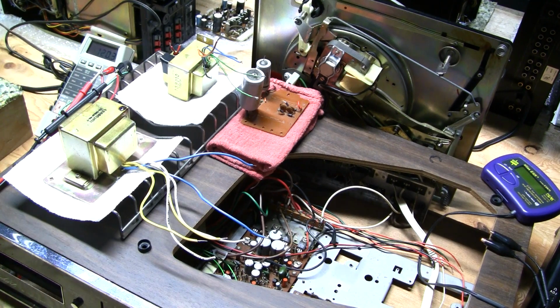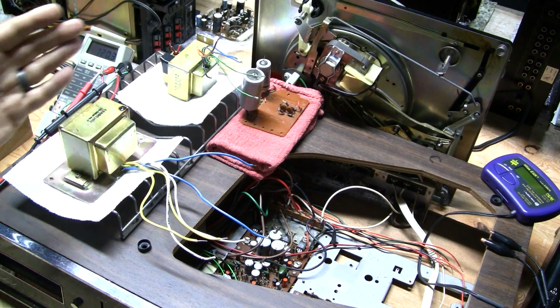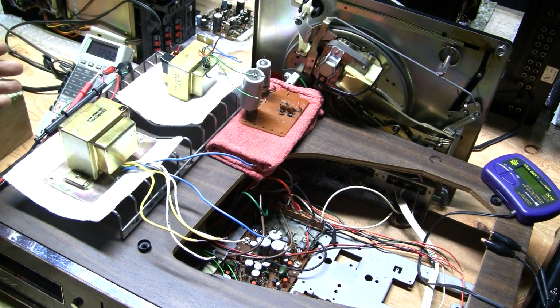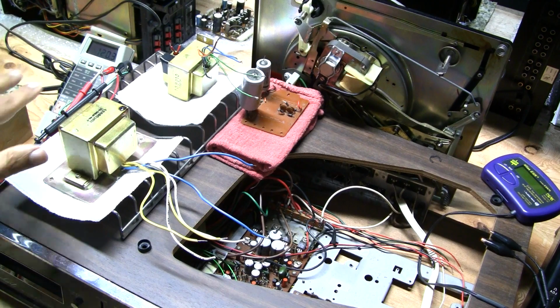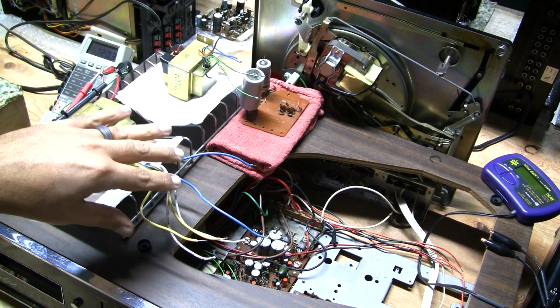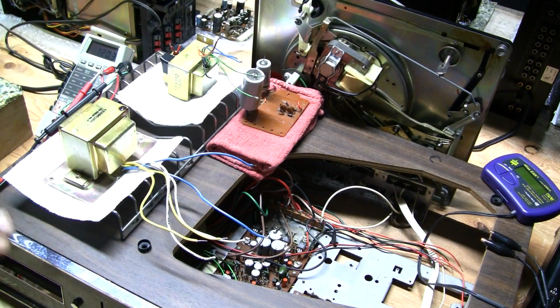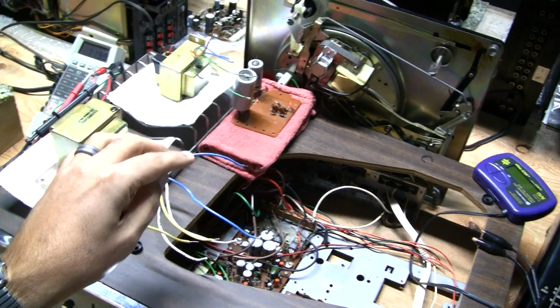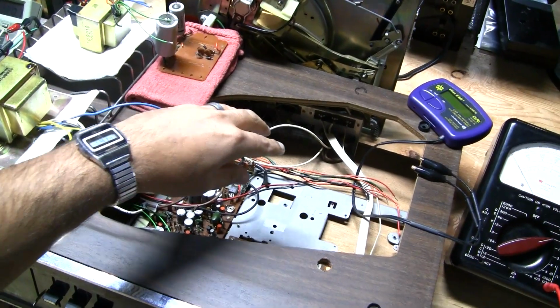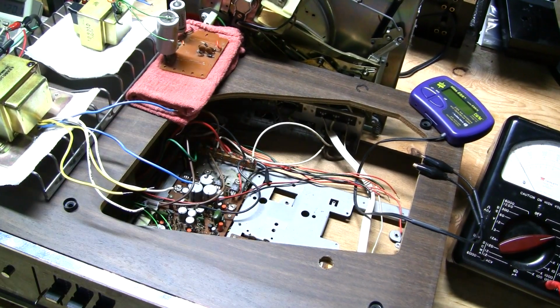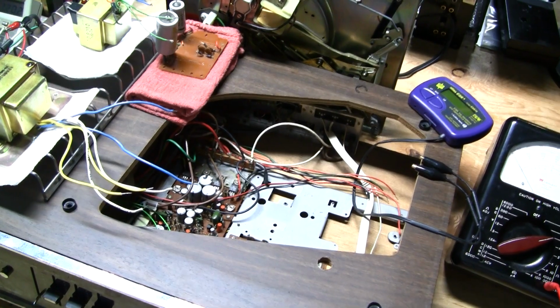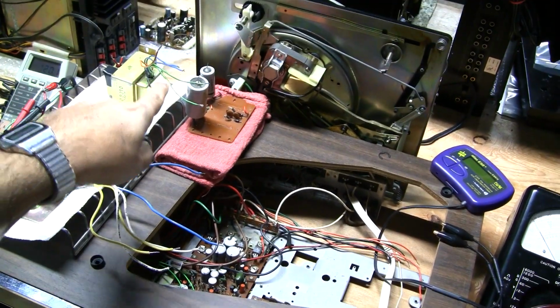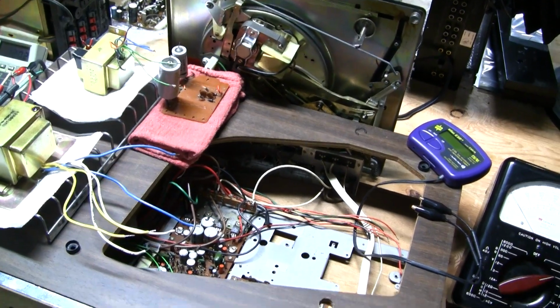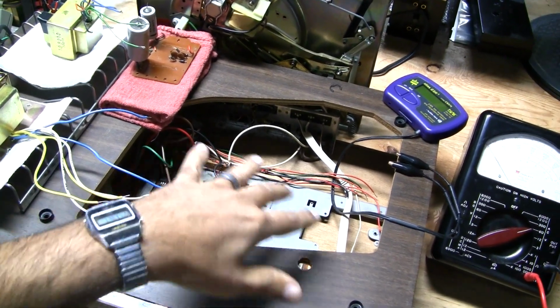So there you go. And then you saw on the good transformer that I fed 120 volts into it, and I still have 120 volts fed into it, by the way, and I have my various voltages coming out that I need for the circuitry contained within this unit. And because our secondary of this transformer was dead, obviously the rest of the unit didn't have power.